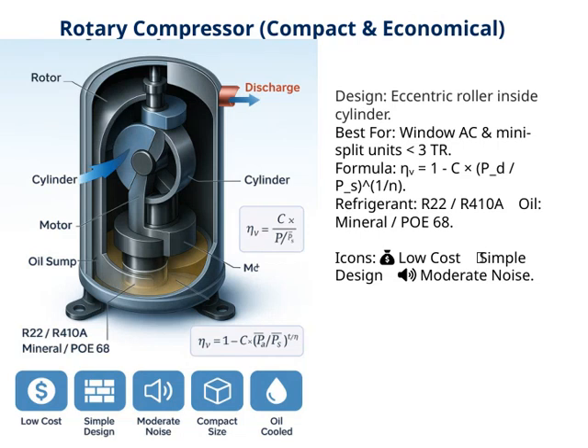Let's take a closer look at the rotary compressor, which is known for being both compact and economical. Its design features an eccentric roller inside a cylinder, which helps keep the unit small while maintaining efficiency. This type of compressor is particularly well suited for window air conditioning units and mini-split systems that are under 3 tons, making it ideal for residential or small commercial applications.